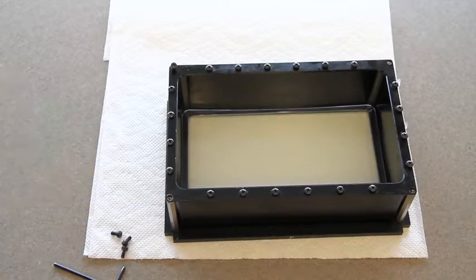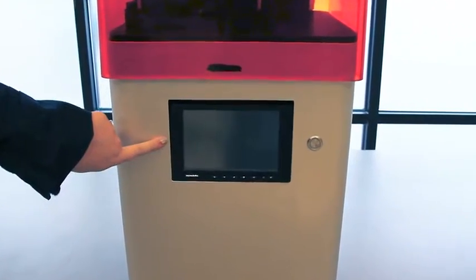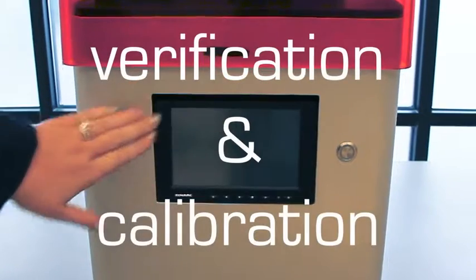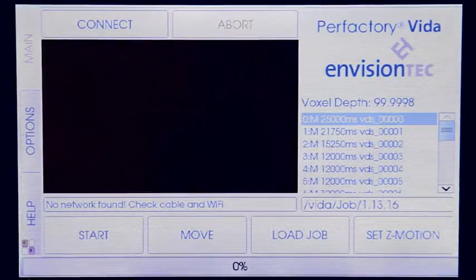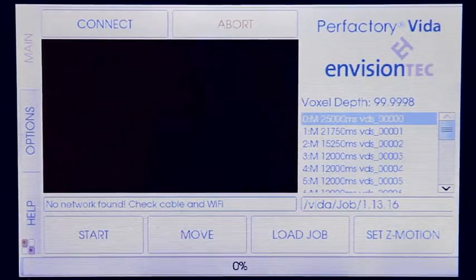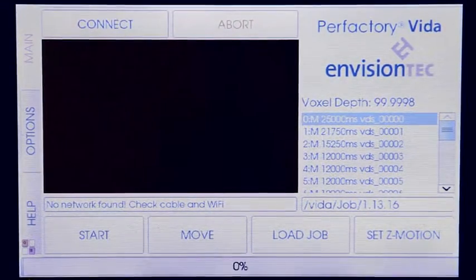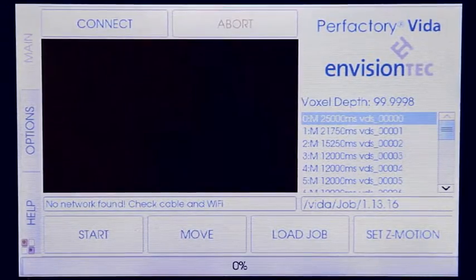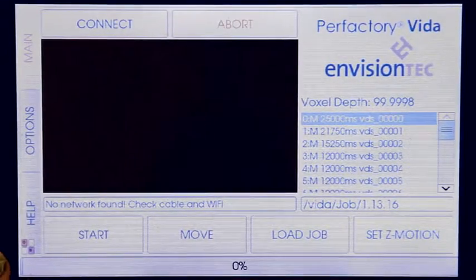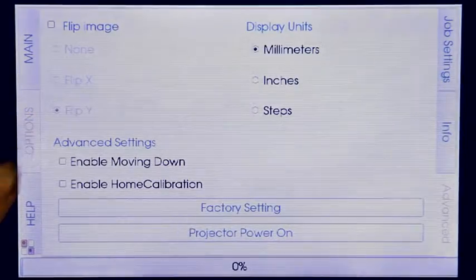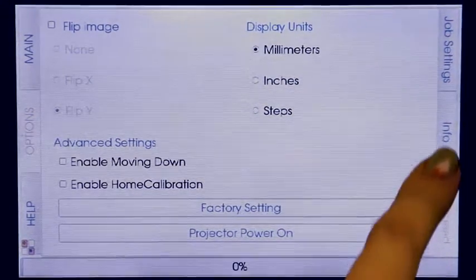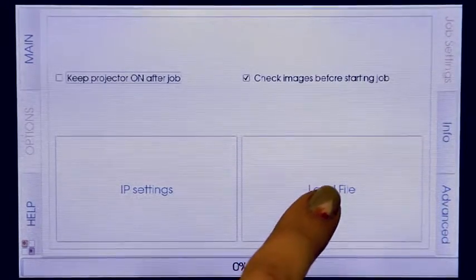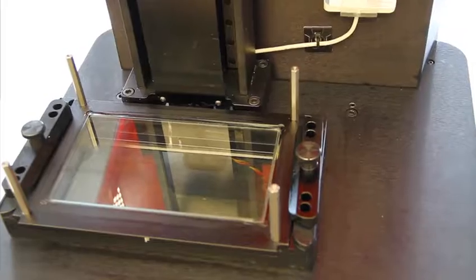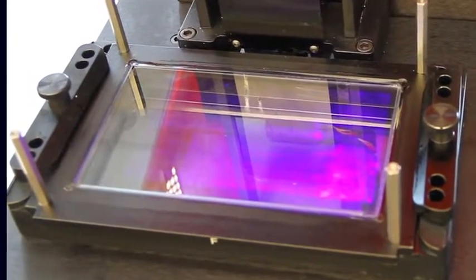to use. The first thing you need to do after unboxing and placing your Vida in its new home is verify that everything is working and calibrated properly. The first thing we're going to do is check the focus and the image parallelism. To do this, I'm going to turn the machine on, go into the Options tab, go into the Job Settings tab, and then select Load File. This will cause the projector to turn on and warm up.